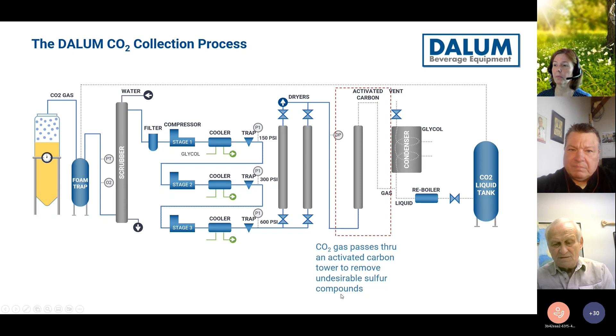Next slide, we go through a condenser. It's basically a coil arrangement, a serpentine coil. In our case, they're different shapes, but ours is a serpentine coil. As the hot gas goes into the bottom, we're running house glycol counterflow through it, and basically as the gas travels up, it cools and turns into droplets of liquid CO2. At the top of the condenser, we have an automatic vent, and what we're looking for there is oxygen, because the gas that cannot be condensed will travel to the top and collect at the top of the condenser. So periodically, based on the contamination with oxygen, we vent that gas off to the atmosphere.